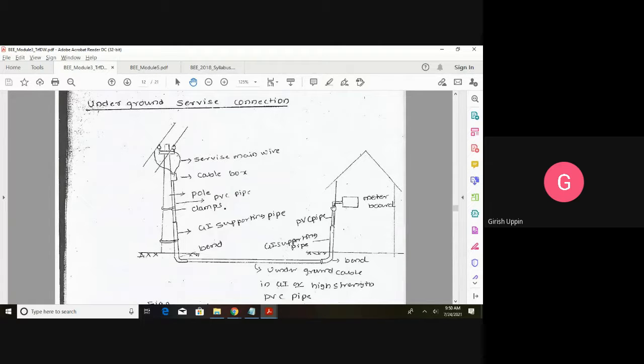The cable will come out and it will come to the meter box, and on top of this they will put the concrete. So this will be very high strength. The PVC pipe or GI pipe, whichever you prefer, can be used. On top of this they put the concrete. So you will not see any wire hanging between the pole and your house. Everything goes inside the ground, and it comes to the meter box.